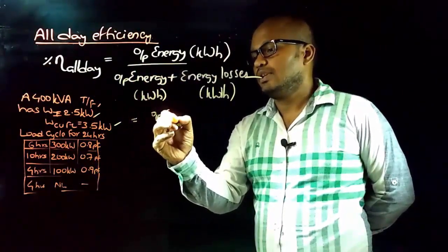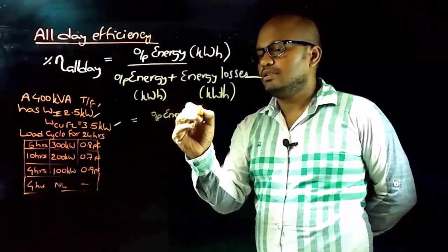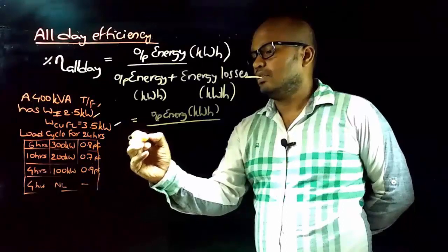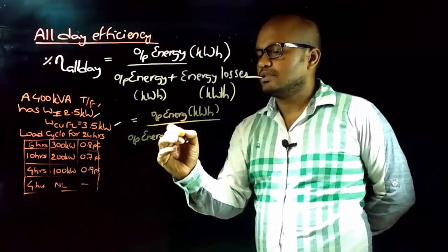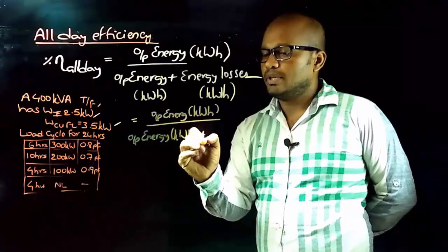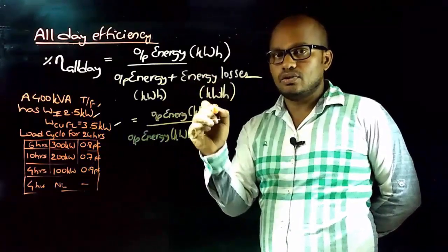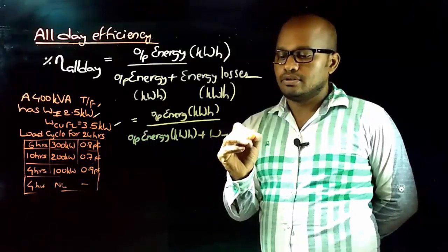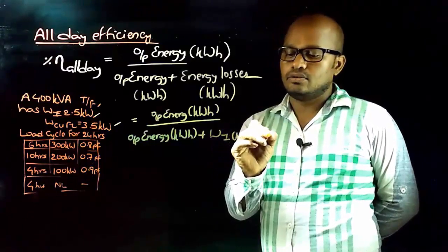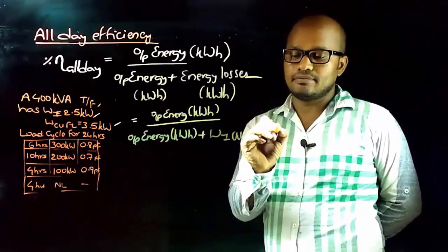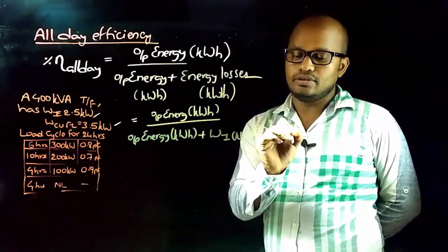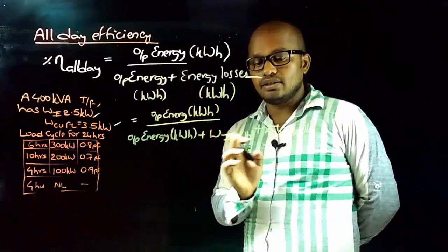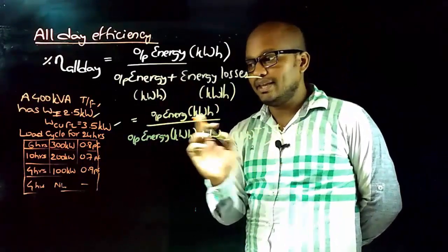The formula is: output energy in kWh divided by output energy in kWh plus energy losses, where energy losses include iron losses and copper losses. Copper losses are equal to x² times Wcu in kilowatt-hours. We first need to find x because it is not directly given.